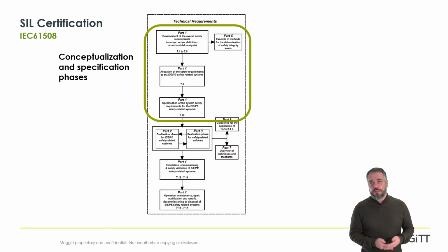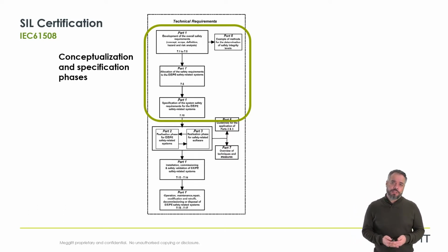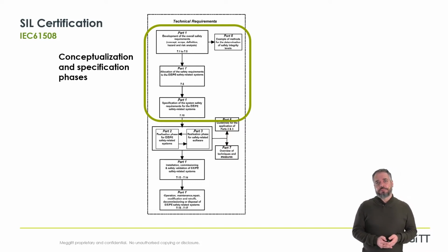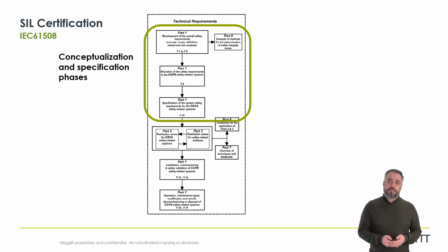In some cases, especially when we talk about elements and not entire safety systems, we know already the SIL target that we want to achieve. In that case, some of the risk and hazard analysis won't be necessary. However, we must be really sure that the SIL level chosen for a certain element fits the application and the market expectations.